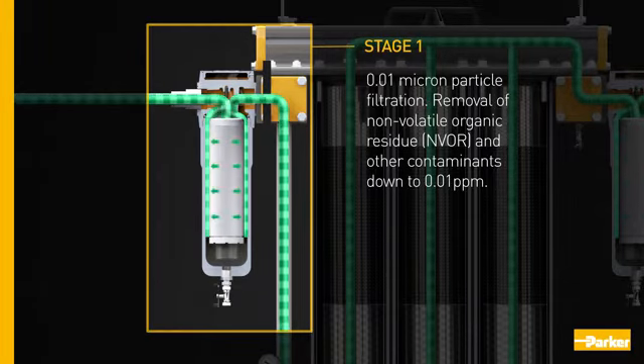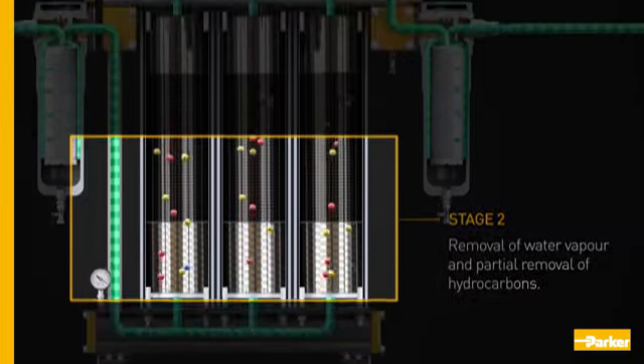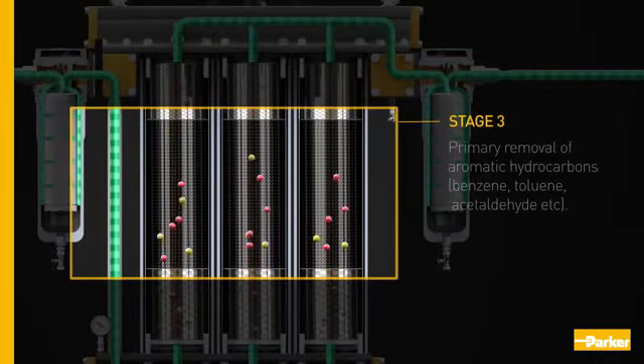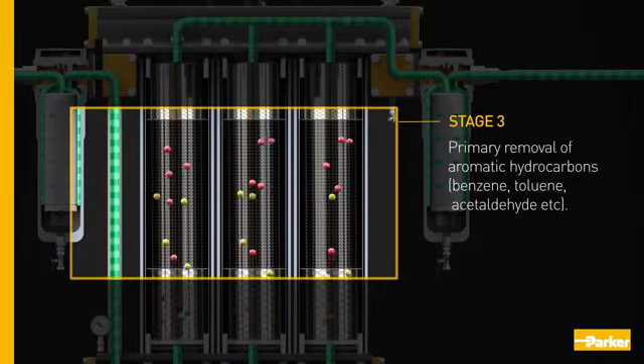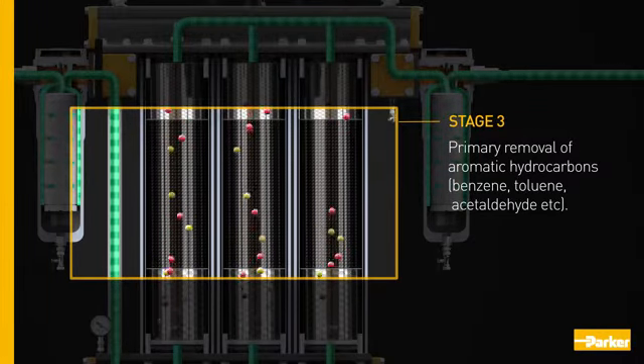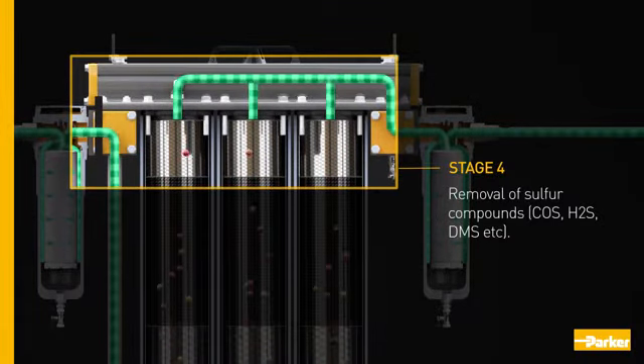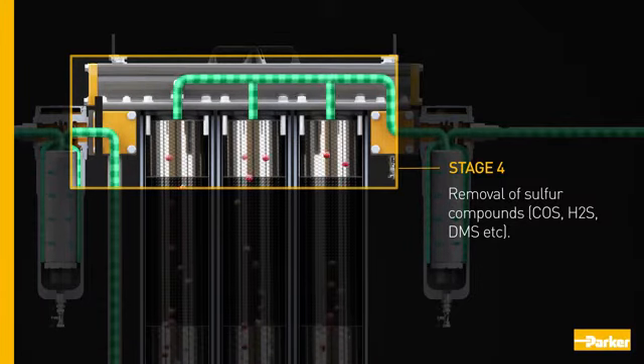Stage 2 and Stage 3 provide partial removal of water vapor and partial removal of hydrocarbons, with primary removal of aromatic hydrocarbons including benzene, toluene, and acetaldehyde. Stage 4 handles removal of sulfur compounds including COS, H2S, and DMS.